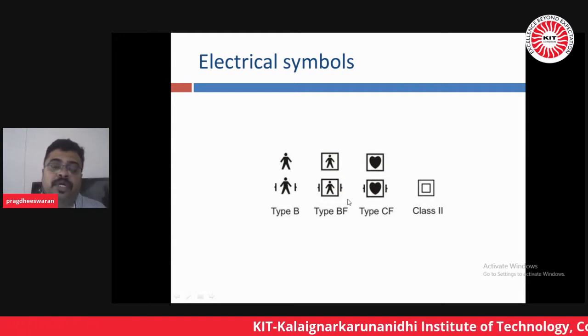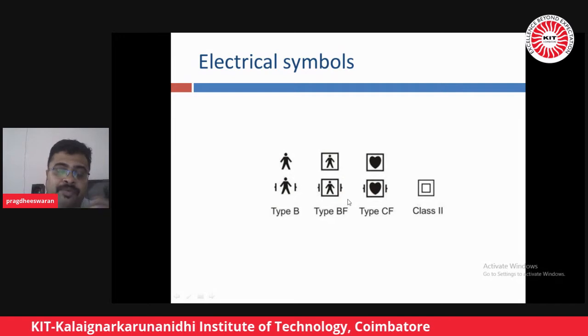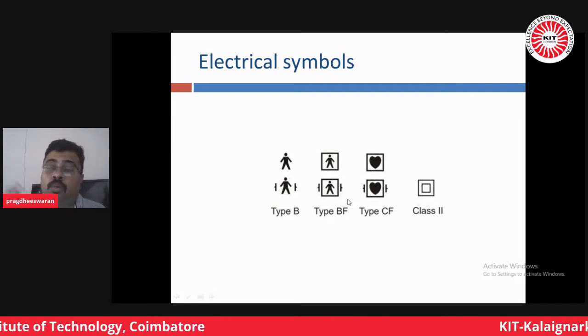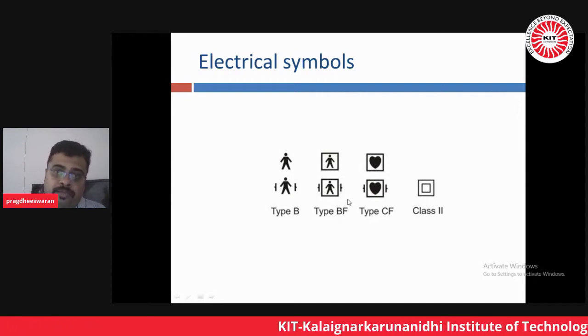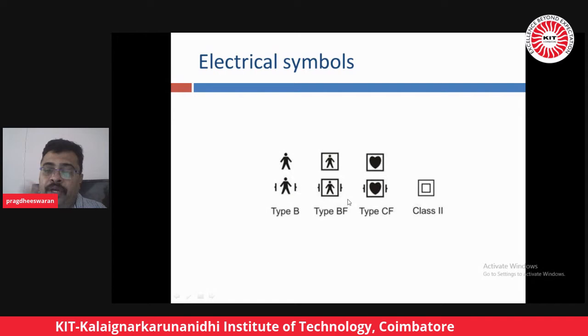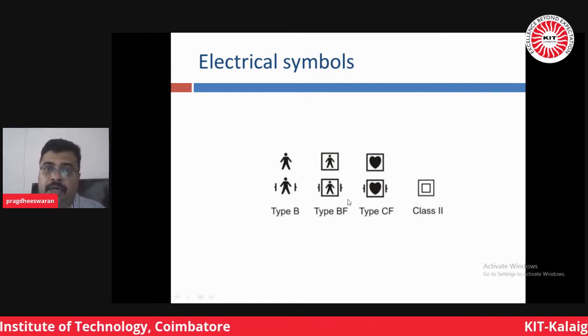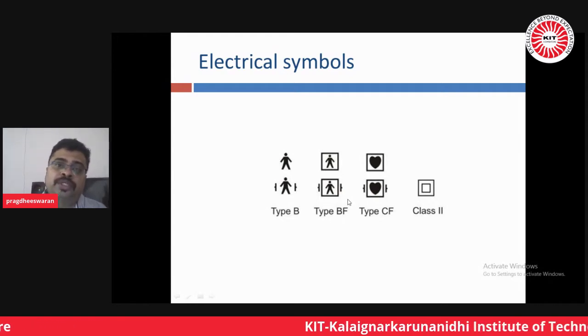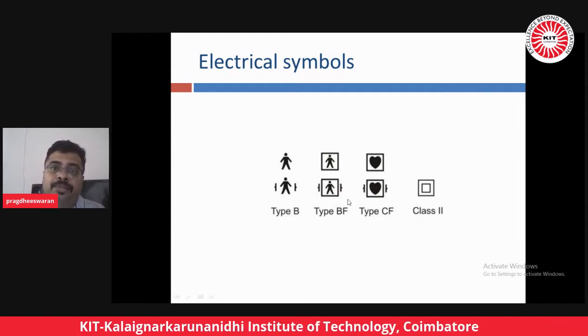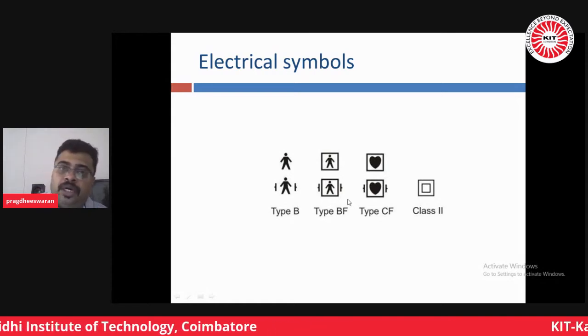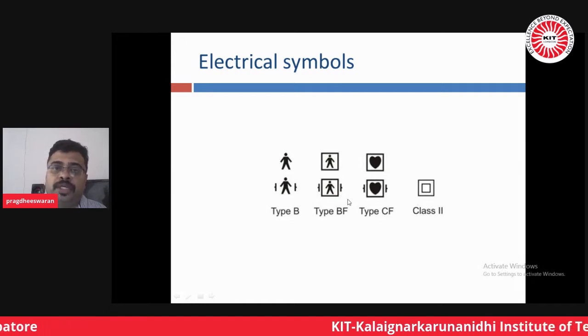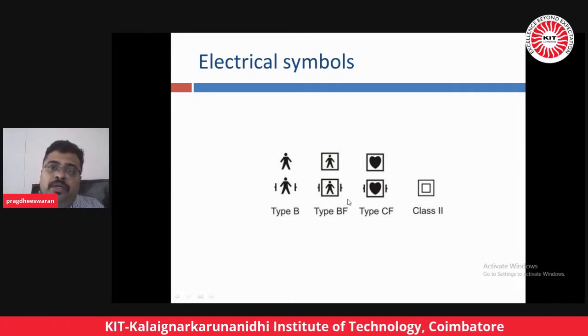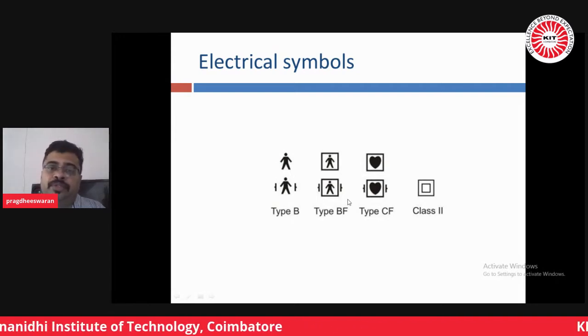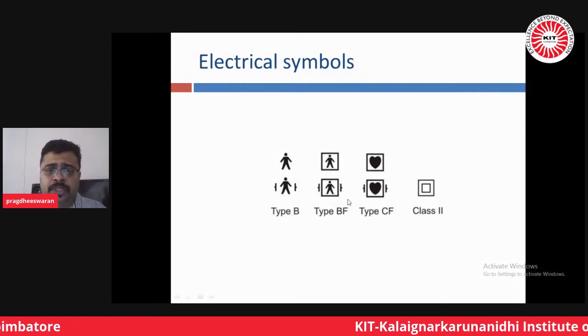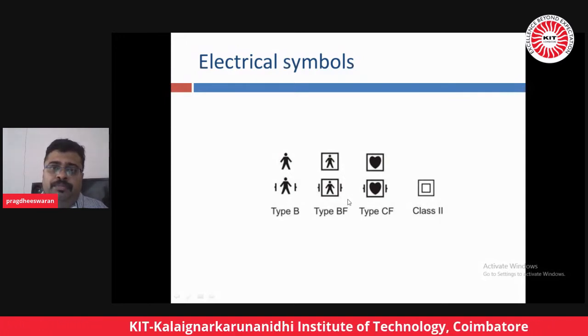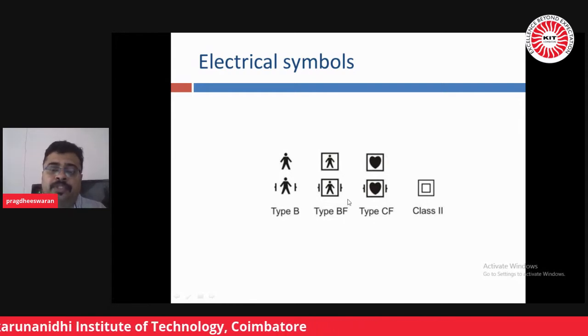But where we make a difference knowledge-wise, we have to understand what kind of classification the equipment has, what leakage current is allowed, what our country's standard for classification of leakage current allows, and what frequency of calibration we are doing. Is there any major service that we changed? Based on that, we apply our common sense to do a calibration. That is where we make the difference between the person who does the calibration without any knowledge and the person who knows something about calibration and the collateral standard procedures. That is one thing. Another thing is certain mistakes associated with calibration.